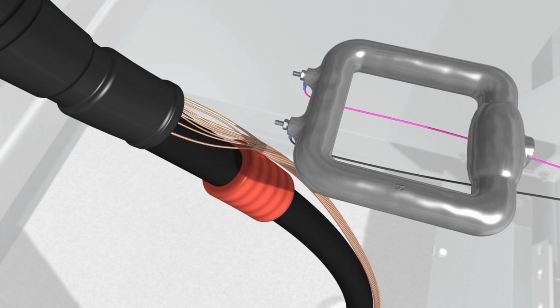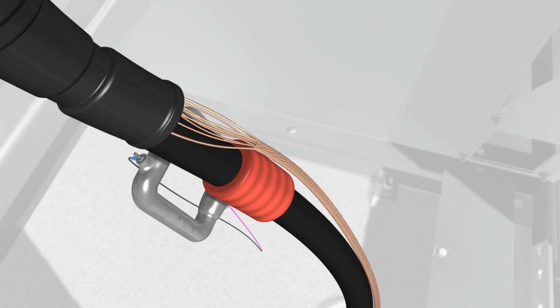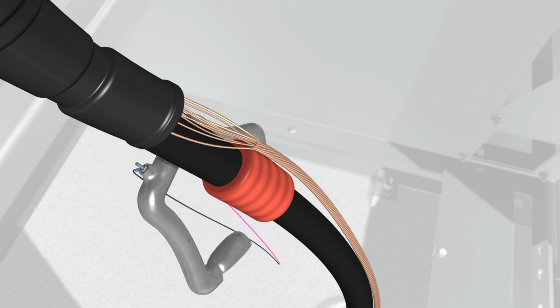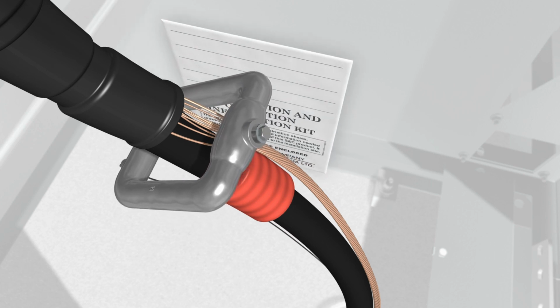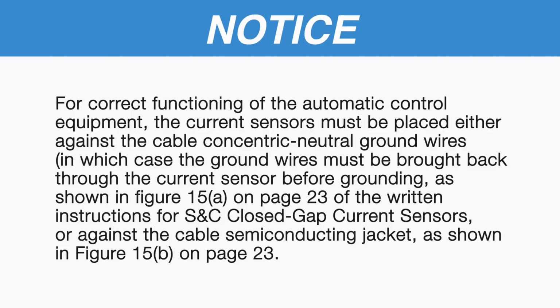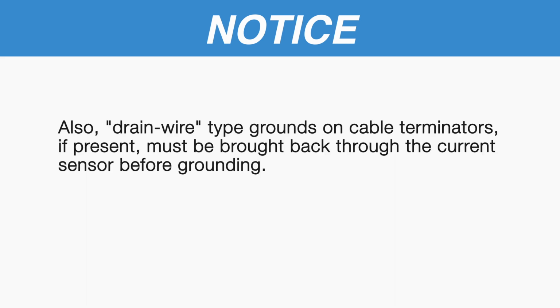Make the control wire lead connections and install the current sensors following the procedures in the applicable instruction sheet and with reference to the applicable wiring diagram, all provided in the Installation and Operation Information Kit supplied with the switchgear. Note: for correct functioning of the automatic control equipment, the current sensors must be placed either against the cable concentric neutral ground wires, in which case the ground wires must be brought back through the current sensor before grounding, as shown in Figure 15A on page 23 of the written instructions for S&C closed gap current sensors, or against the cable semiconducting jacket, as shown in Figure 15B on page 23. Also, drain wire type grounds on cable terminators, if present, must be brought back through the current sensor before grounding.